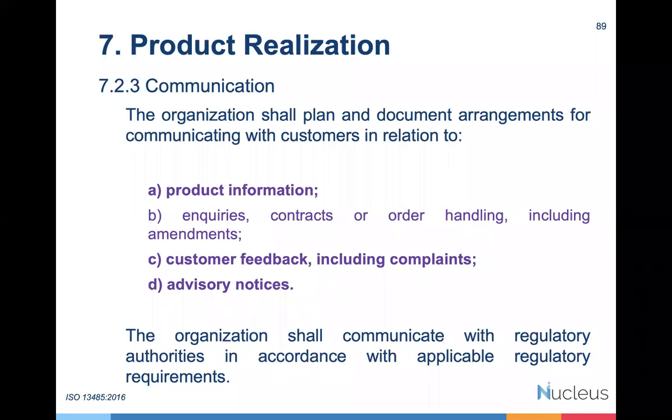See, advisory notices are issued by the organization. They are not issued by the regulators. They are only issued by the company, after delivery of a medical device, to provide some supplementary information or advice. It is not always a negative advisory notice. Look at the word, it's advice. This is given by the manufacturer for the purpose of how to use a medical device, or if there is any modification of a medical device, or to return the device, a recall, right?